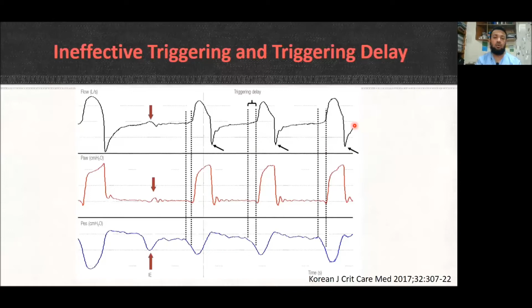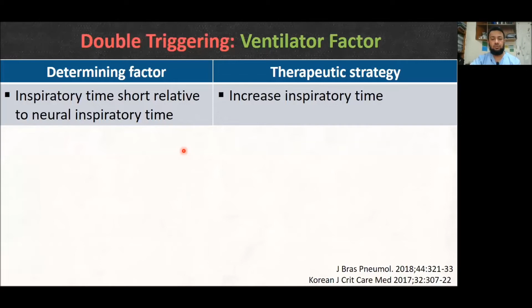The ventilator delivers two subsequent breaths when the patient is taking only one breath, and it happens if the inspiratory time is set too short. Say the patient's inspiratory time is not set appropriately. For an infant or an older child of 5 years, inspiratory time should be 1 second. But if we set 0.5 second, that is too short. In that case, double trigger may occur, and inspiratory time has to be set appropriately. Or it can occur if a low tidal volume or low peak PIP is set.